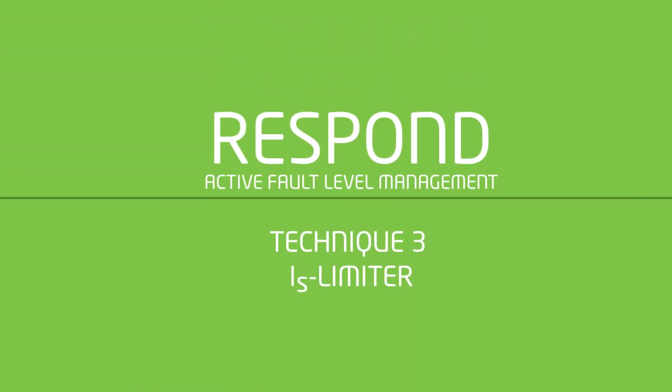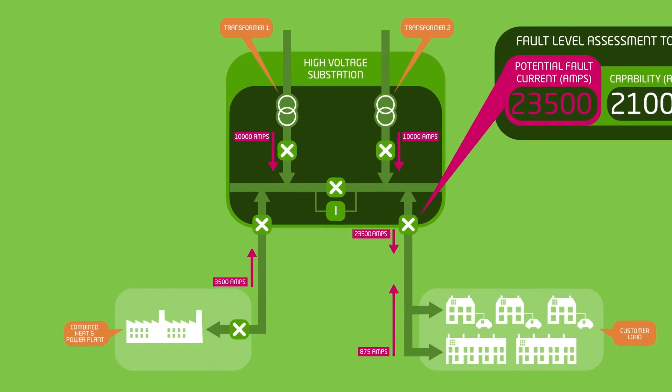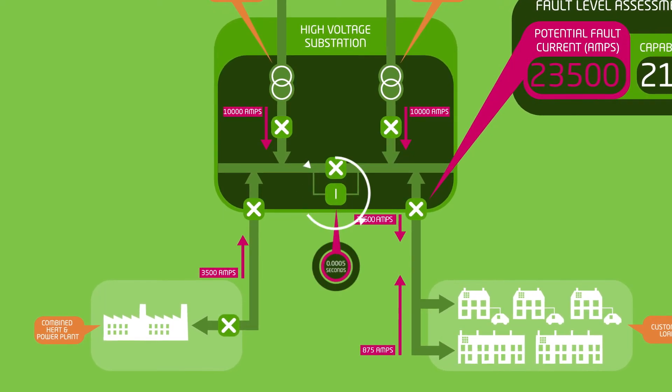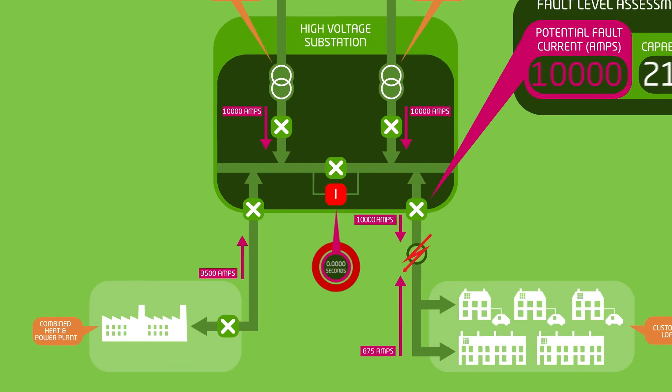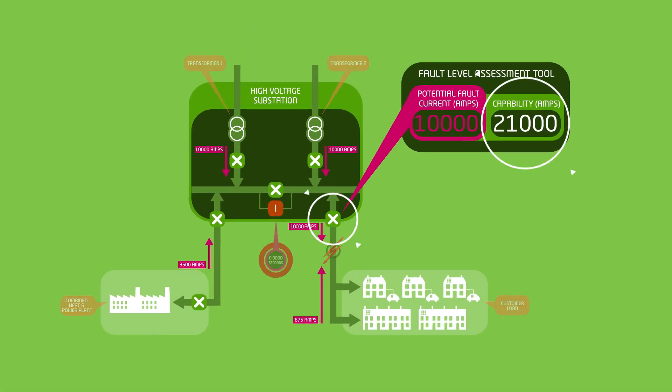Our third technique is a fault current limiting device known as the IS limiter. When a fault occurs, the IS limiter is activated within half a millisecond, so fast that neither the transformer nor the generator contribute to the fault current. This reduces the total amps flowing to the fault to a level well within the capability of the high voltage circuit breaker, and prevents damage to the network.